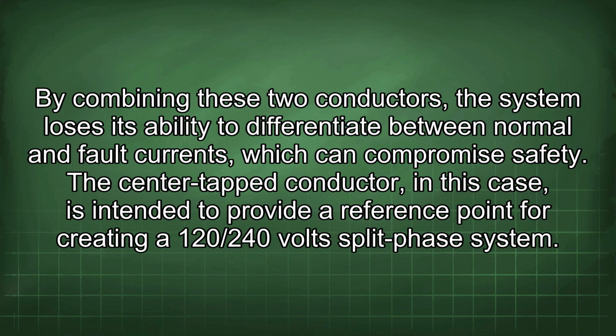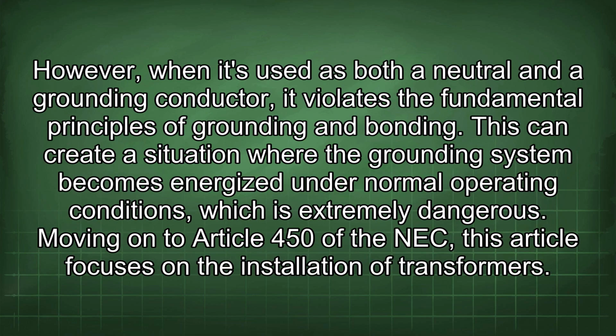By combining these two conductors, the system loses its ability to differentiate between normal and fault currents, which can compromise safety. The center-tapped conductor, in this case, is intended to provide a reference point for creating a 120/240 volt split-phase system. However, when it's used as both a neutral and a grounding conductor, it violates the fundamental principles of grounding and bonding. This can create a situation where the grounding system becomes energized under normal operating conditions, which is extremely dangerous.